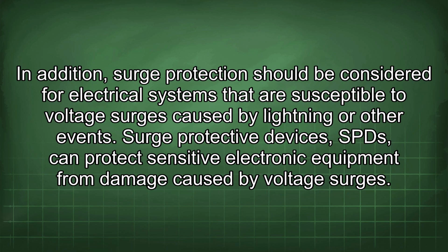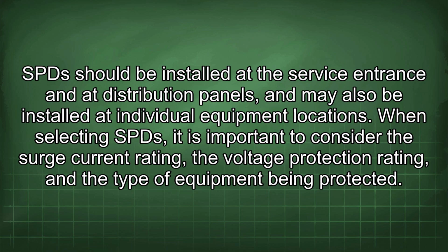In addition, surge protection should be considered for electrical systems that are susceptible to voltage surges caused by lightning or other events. Surge protective devices, SPDs, can protect sensitive electronic equipment from damage caused by voltage surges. SPDs should be installed at the service entrance and at distribution panels, and may also be installed at individual equipment locations. When selecting SPDs, it is important to consider the surge current rating, the voltage protection rating, and the type of equipment being protected.